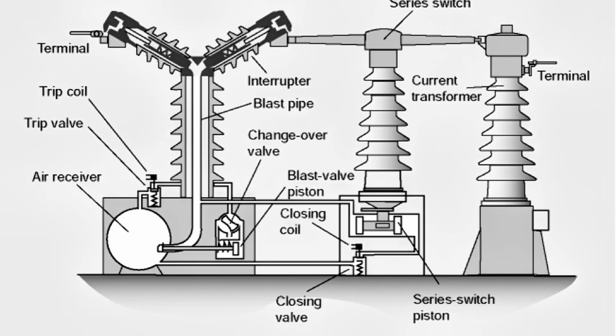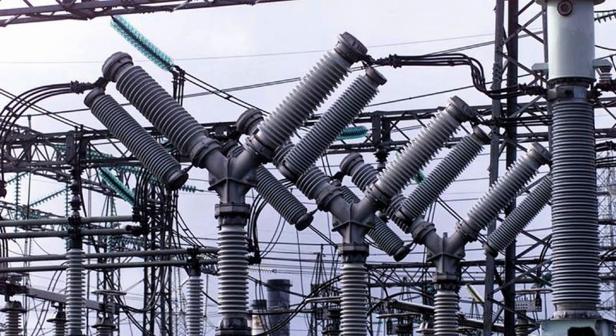The radial blast type is designed to provide high arc extinction capability, even in cases where the arc is highly unstable. By directing the compressed air radially outward, the radial blast type can effectively cool and extinguish the arc, reducing the risk of damage to the circuit breaker and other equipment. Its design makes it well suited for applications where high-speed fault clearance is essential for maintaining system stability and reliability. By providing high arc extinction capability, the radial blast type helps to minimize downtime and maintenance costs, ensuring reliable operation of the power system.